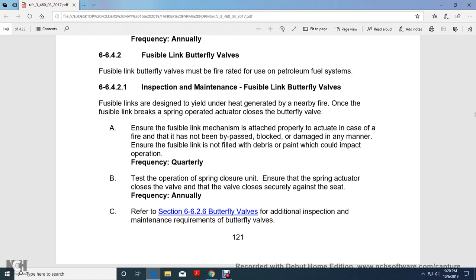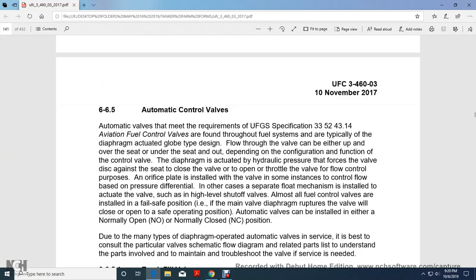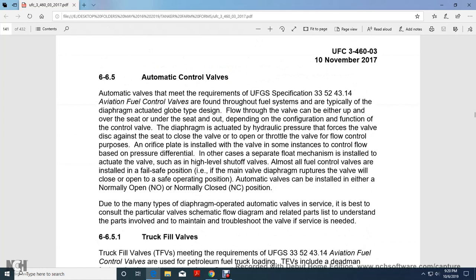6626 butterfly valves, additional inspection of the requirements of butterfly valves. Automatic control valves. Automatic valves meet the requirements of the Unified Guidelines spec 3352-4314 for aviation fuel control valves throughout the fuel system, typically with a diaphragm-actuated globe type design. Flow through the valve can be either up or over the seat, or under the seat and out, depending on the configuration and function of the control valve.